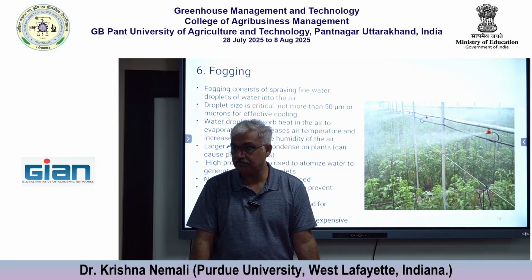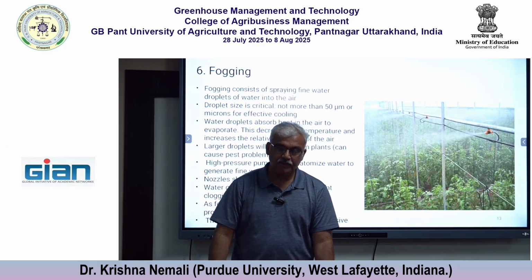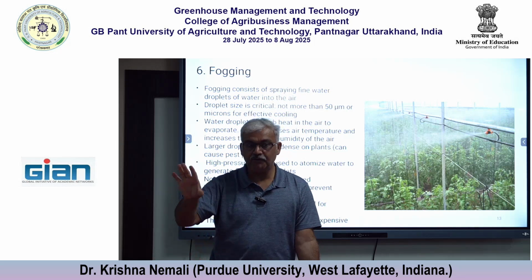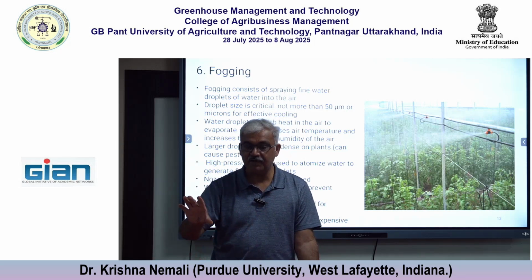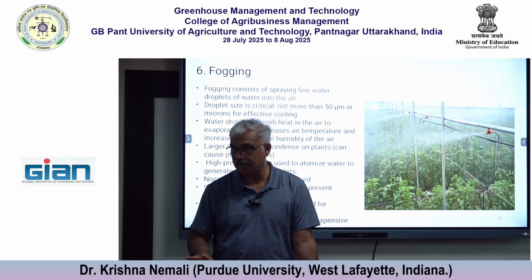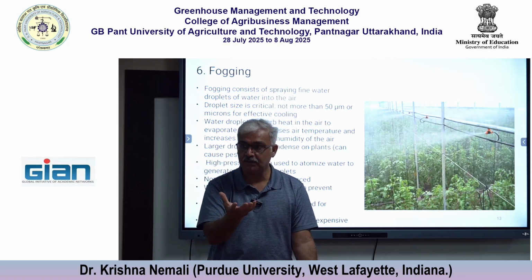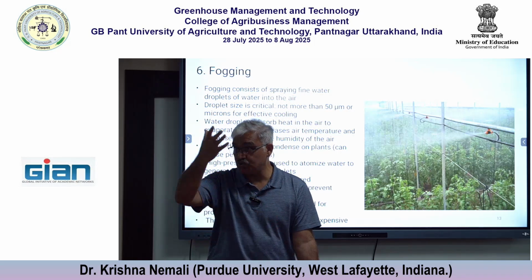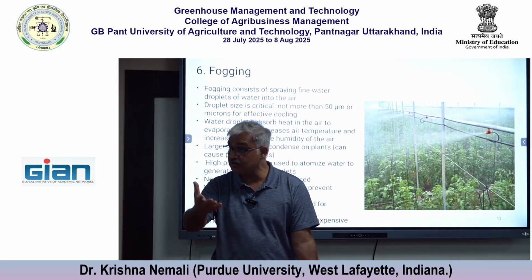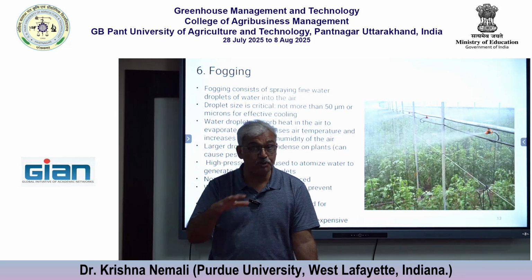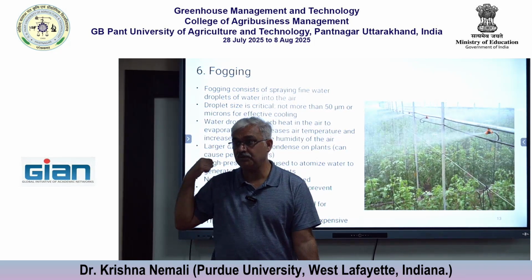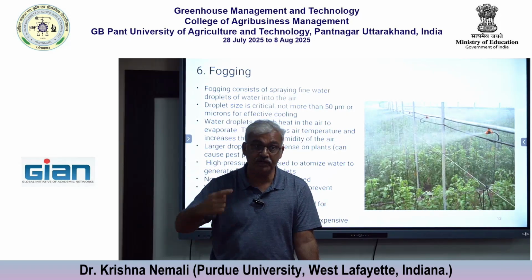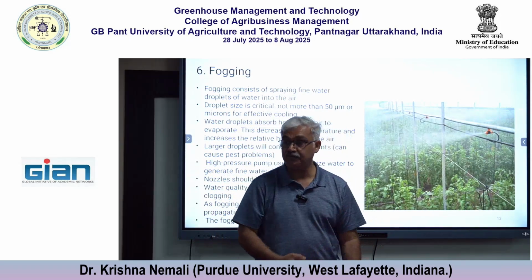Yeah. So will those options be a better investment within a country like India? Well, first of all, if you are in a place like Udaipur where there's a lot of lakes, I'm expecting that the humidity is going to be higher because water is evaporating from the lakes. We have a very similar situation where I live. Lake Michigan is one of the huge lakes, and we have a huge greenhouse next to Lake Michigan, and it's a humid area. This system was not effective at all to begin with. There, the greenhouses went for a coil system. I would recommend that for such situations.